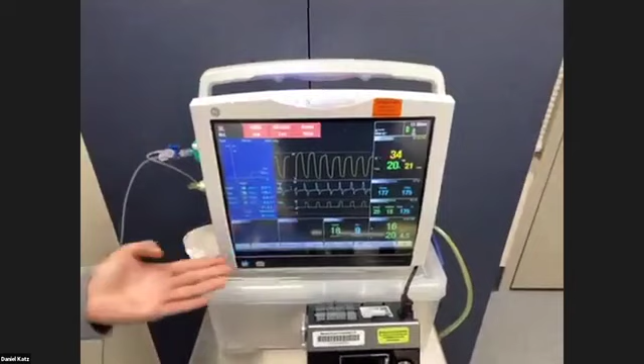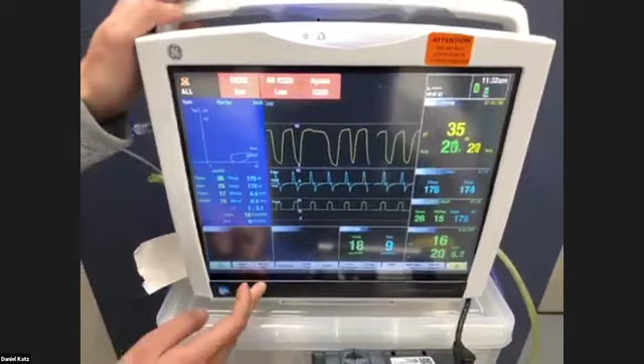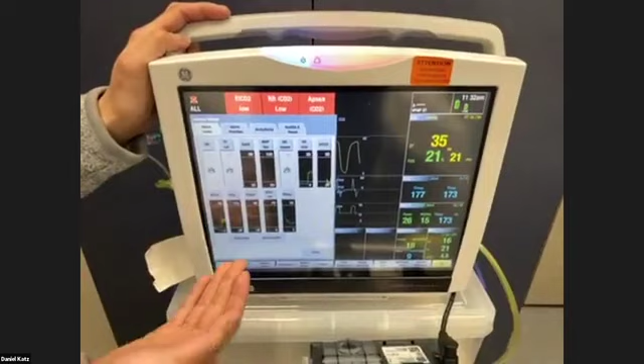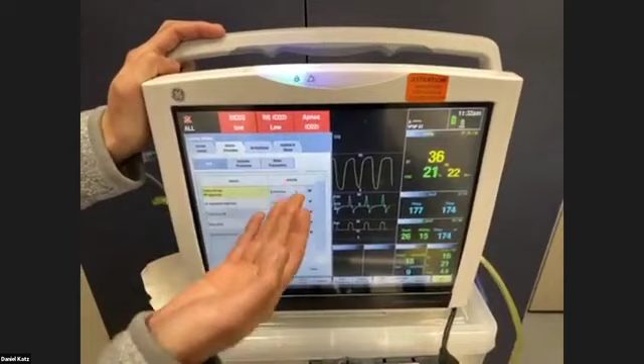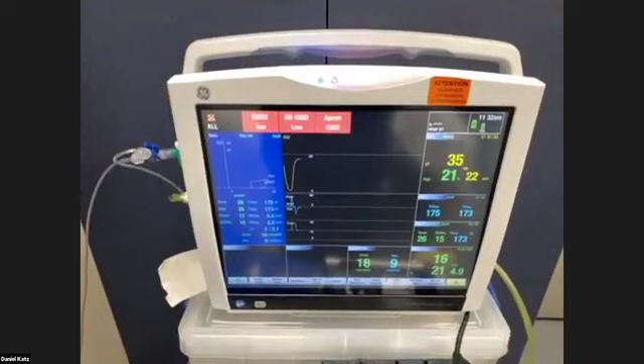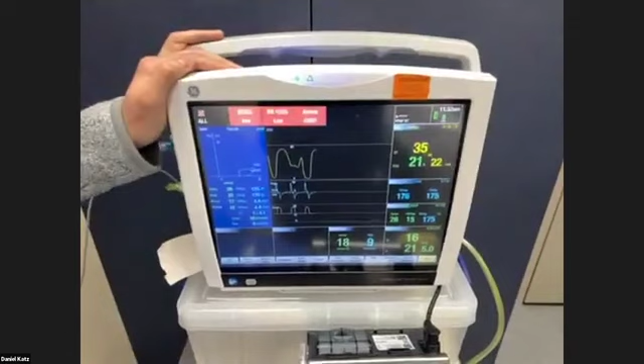Here, we also are able to see the pressure volume curves in our spirometry unit. We can detect a ventilator disconnect, but we can also diagnose potential situations, including ventilator dysynchrony, hemodynamic instability, and so forth. And this module especially, even though you don't see it here, has the capability of attaching SpO2, and over here will also be a dedicated spot for invasive airway monitoring that can be adjusted and customized for every patient. And as you can see here, we are able to customize our alarm parameters based on every patient's different ventilatory techniques. We can also set alarm priorities to really make sure that we don't have any alarms that are not reasonable.